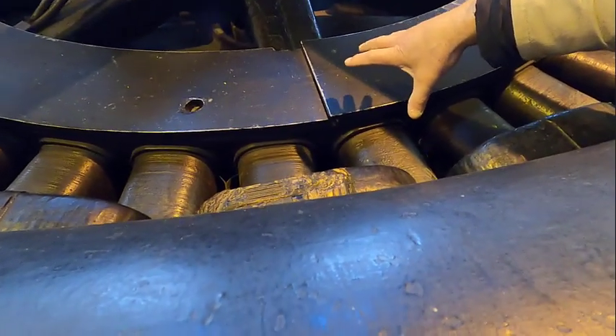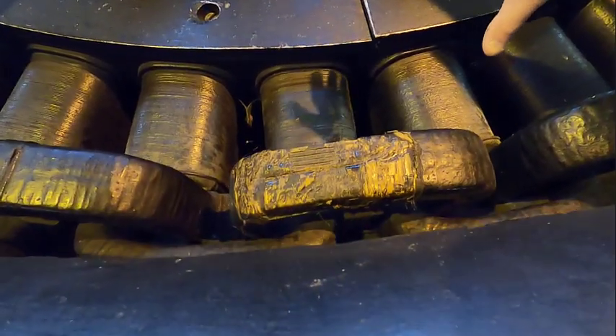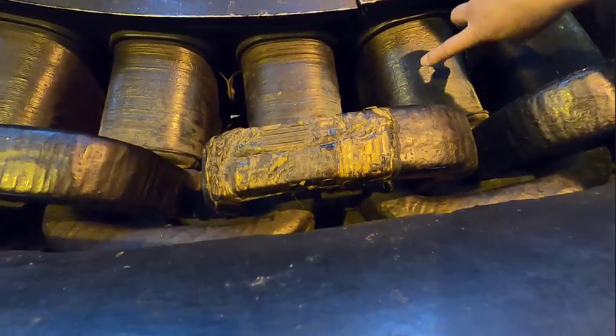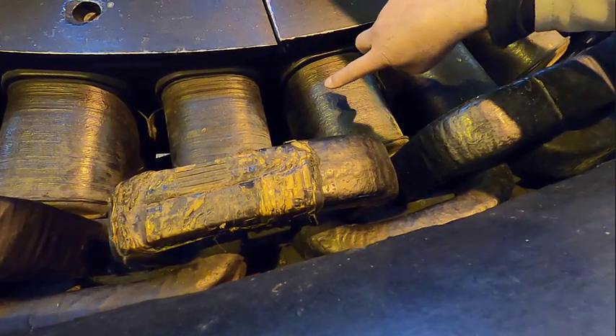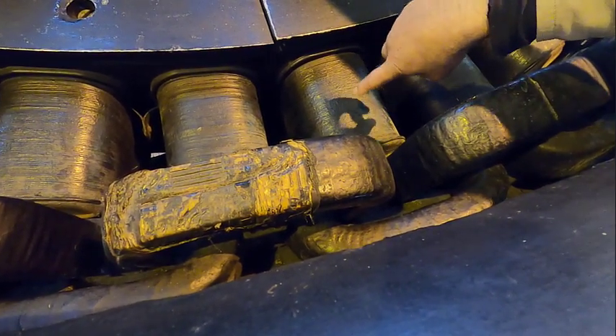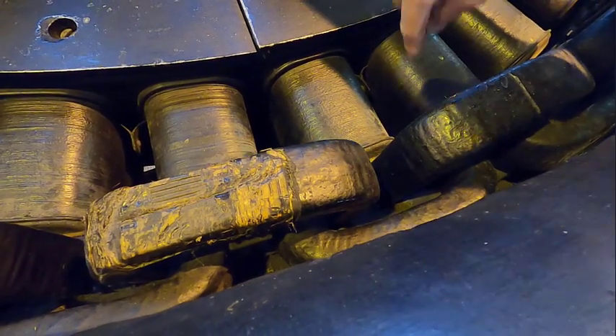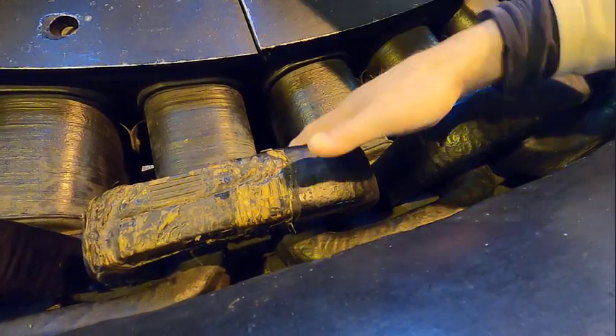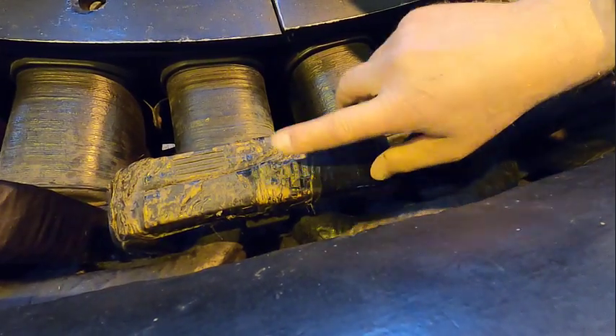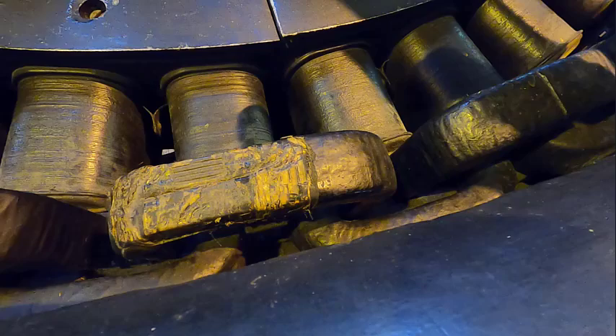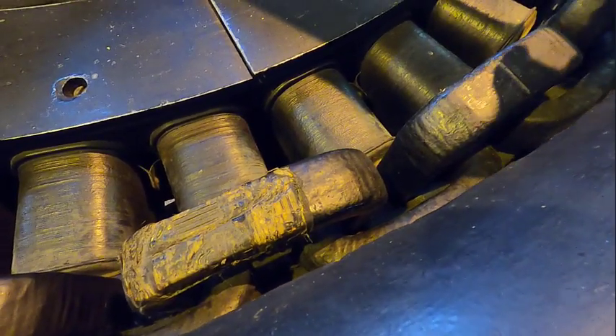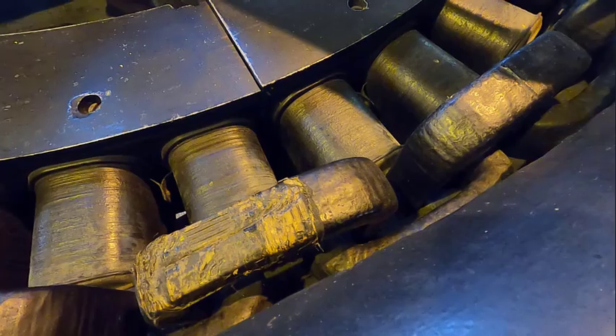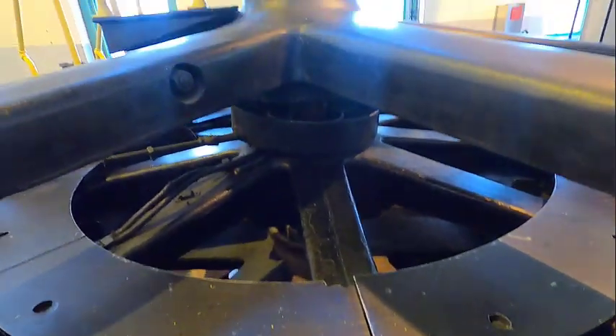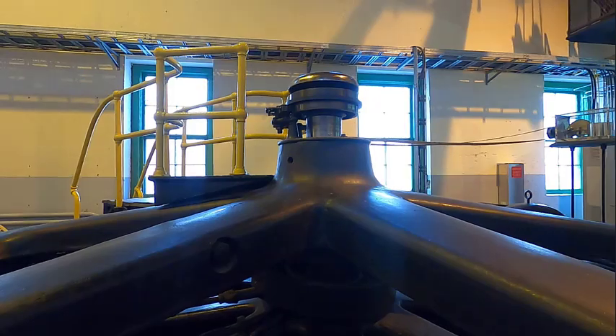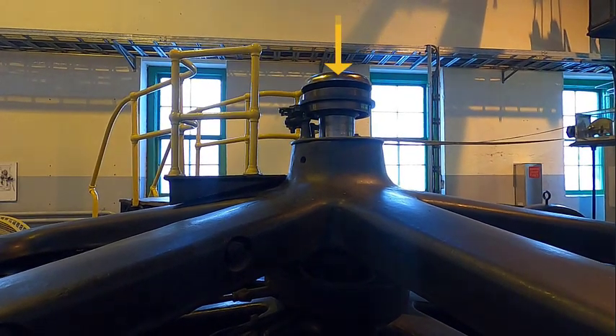And this part inside of it here is called the rotor. This is the part that would be spinning by force of the water when it was running. Then on the outer edge of the rotor are these poles which have DC power running through them, and they're what create the large magnetic force to create the power in the non-moving stator coils here. So your magnets are spinning, not the wire. Right. Exciter. Yeah.